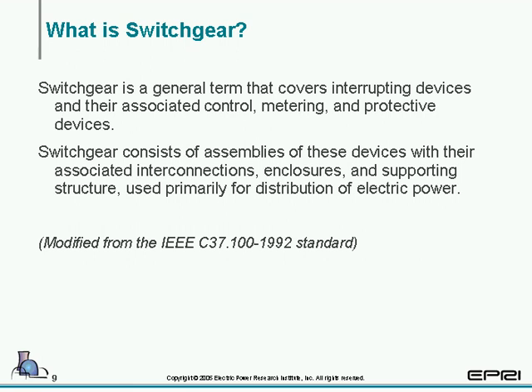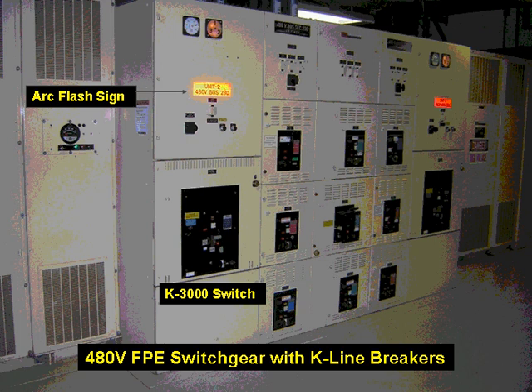IEEE has a basic standard which states that switchgear is a general term that covers interrupting devices and their associated control, metering, and protective devices. Switchgear consists of assemblies of these devices with their associated interconnections, enclosures, and supporting structures used primarily for the distribution of electric power. And on your screen right now, you'll actually see a lineup, and you're going to see here we have a transformer. On the other side, we have another transformer. We have main breakers coming off the transformer. And in the center, you'll see a tie breaker that is opened and racked out. And we'll also see some meters on both sides above the mains.